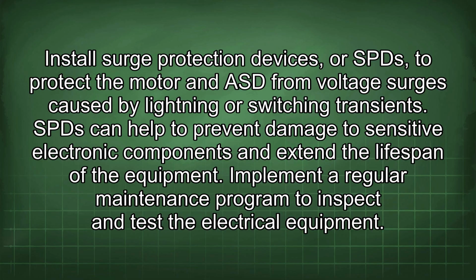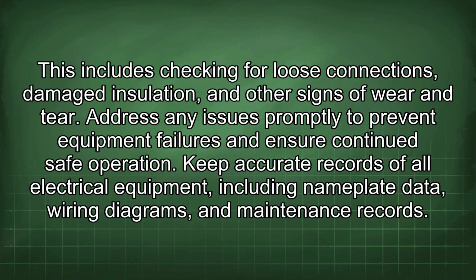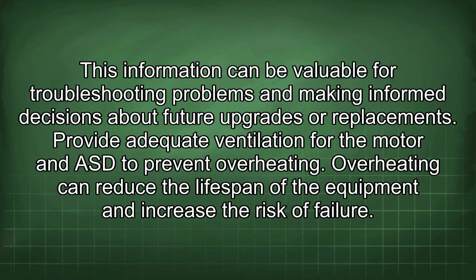Implement a regular maintenance program to inspect and test the electrical equipment. This includes checking for loose connections, damaged insulation, and other signs of wear and tear. Address any issues promptly to prevent equipment failures and ensure continued safe operation. Keep accurate records of all electrical equipment, including nameplate data, wiring diagrams, and maintenance records. This information can be valuable for troubleshooting problems and making informed decisions about future upgrades or replacements.